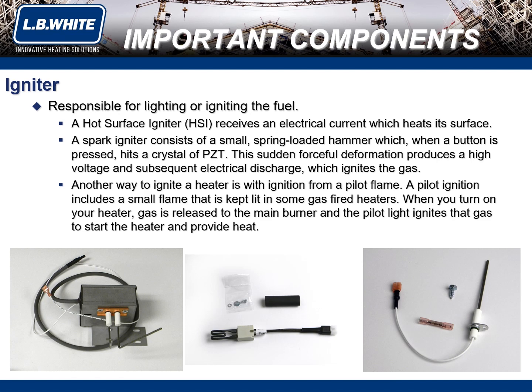A hot surface igniter, HSI, receives an electrical current which heats its surface. A spark igniter consists of a small, spring-loaded hammer which, when a button is pressed, hits a crystal of PZT. This sudden forceful deformation produces a high voltage and subsequent electrical discharge, which ignites the gas. And a pilot ignition includes a small flame that is kept lit in some gas-fired heaters. When you turn on your heater, gas is released to the main burner and the pilot light ignites that gas to start the heater and provide heat.